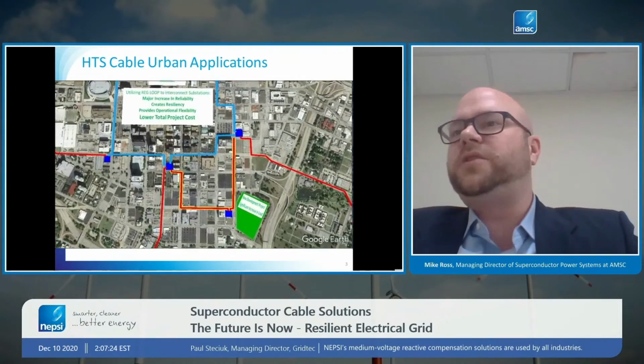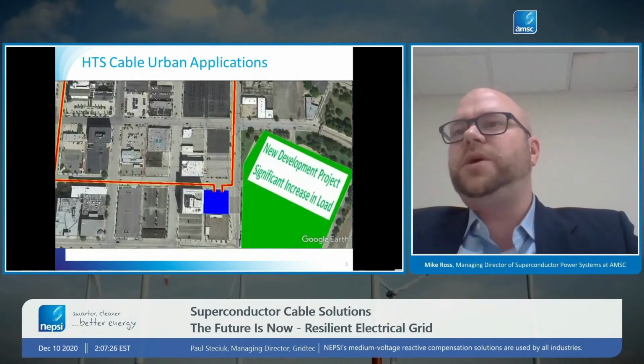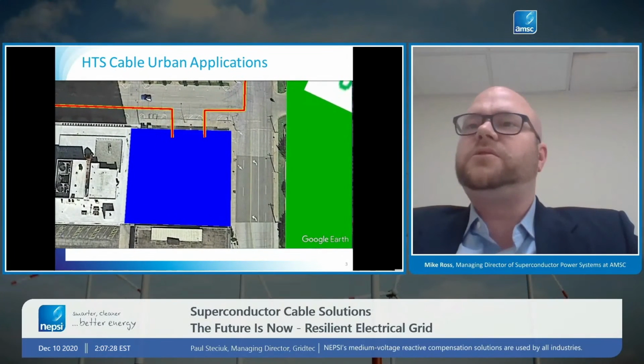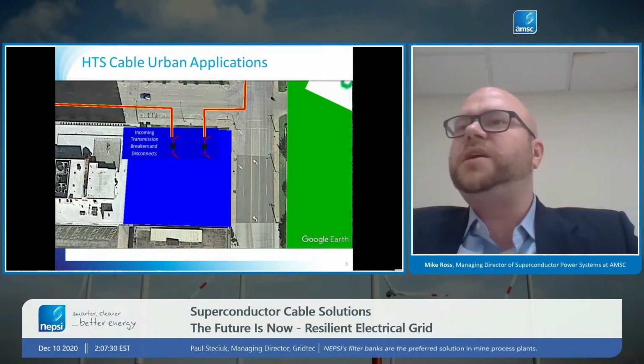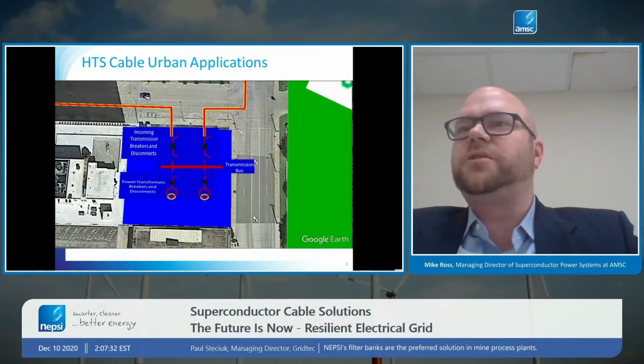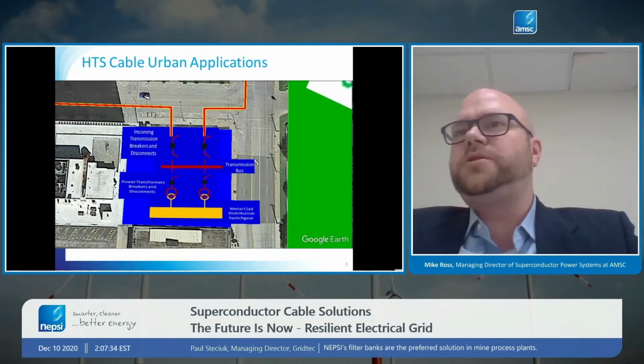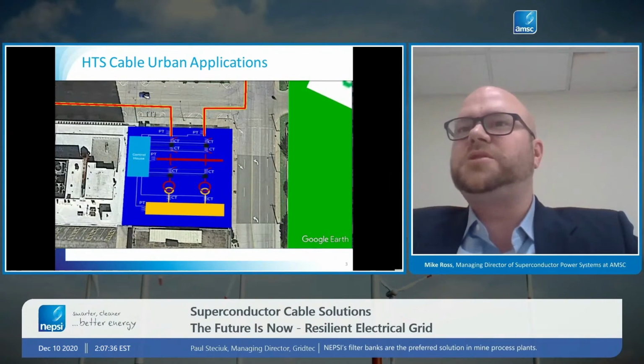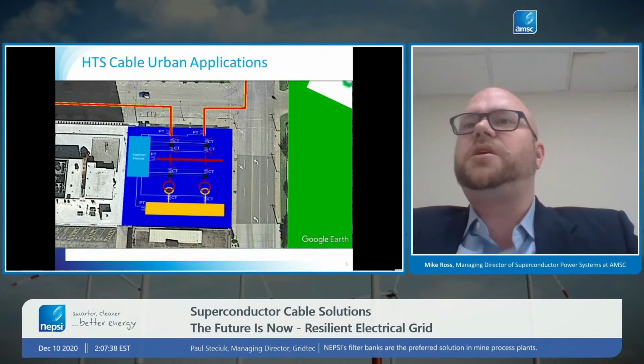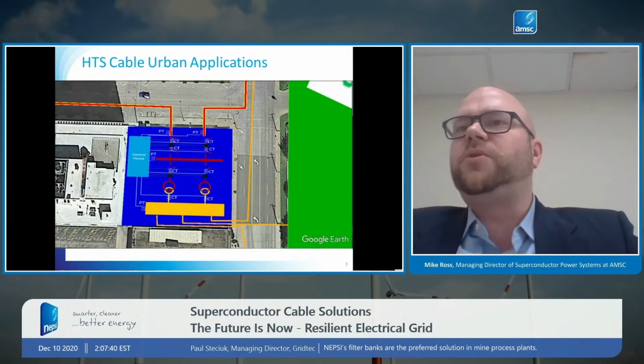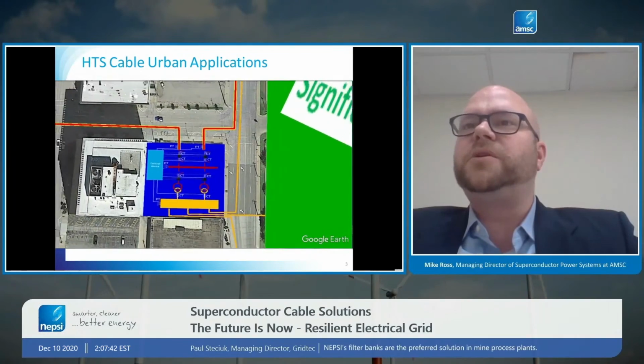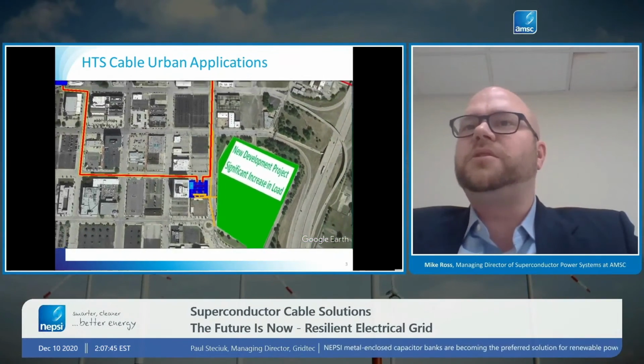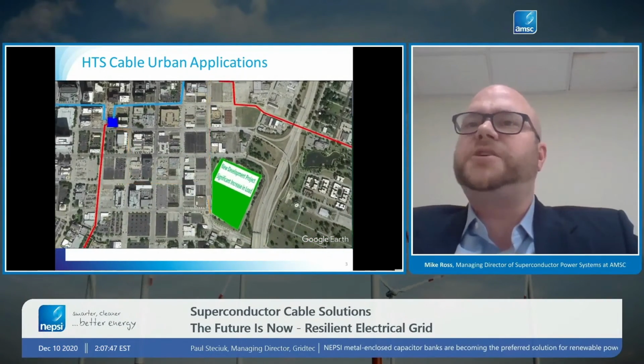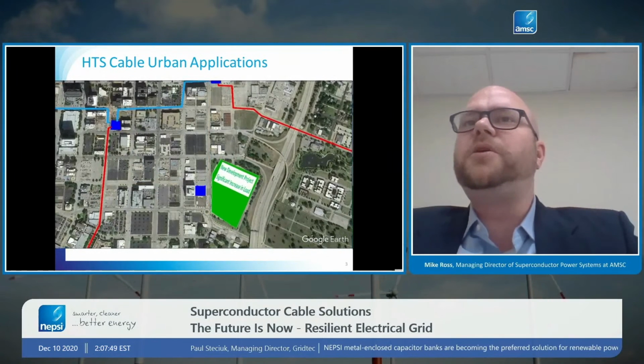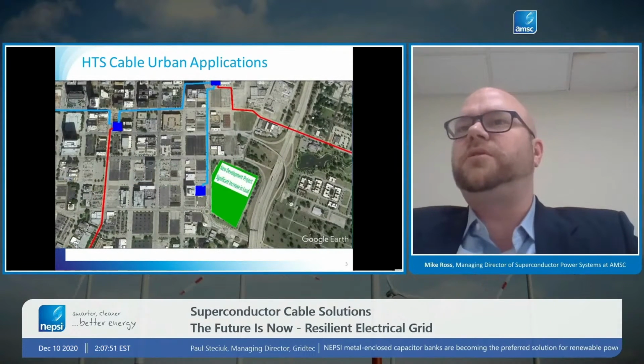need to build a new substation. And traditionally, the way that we might do that is we'd put in a new substation and we'd connect that substation to the transmission grid, usually with 2 or more transmission cables at transmission high voltage. And then we install a full substation with transformers and redundant components, a big control house, and so on. These are big projects, and they can be hundreds of millions of dollars in urban areas.